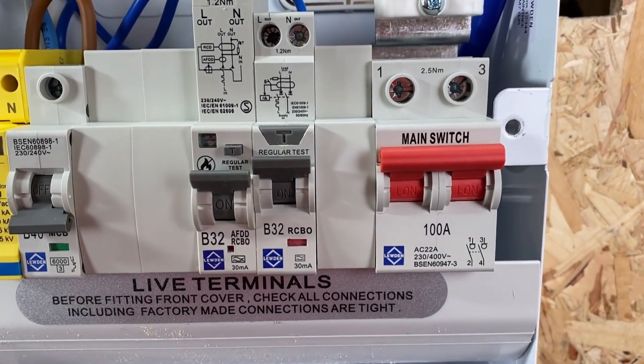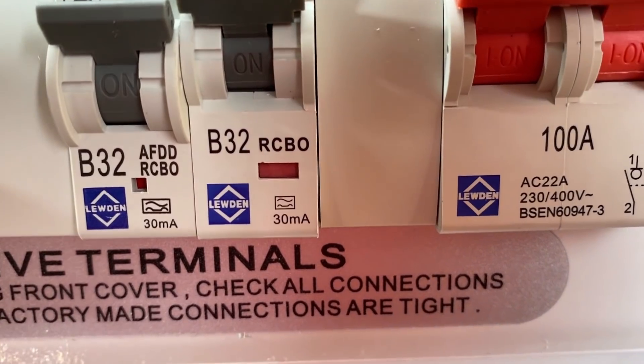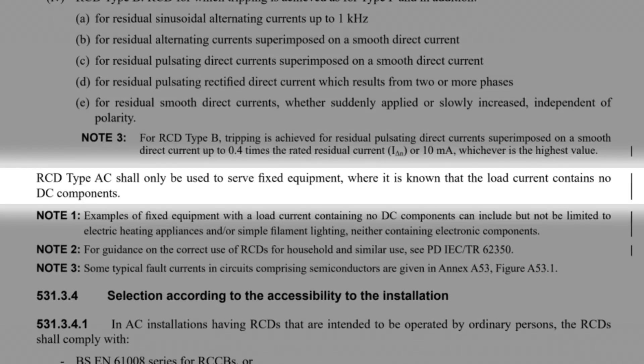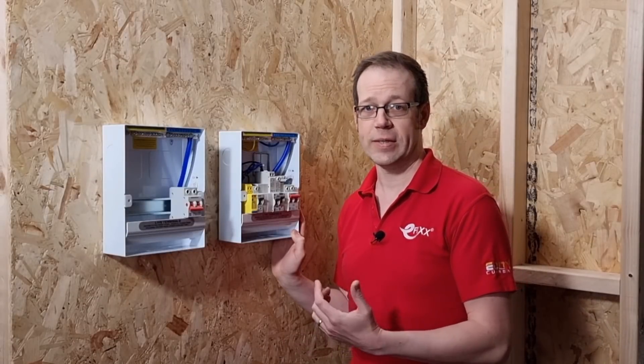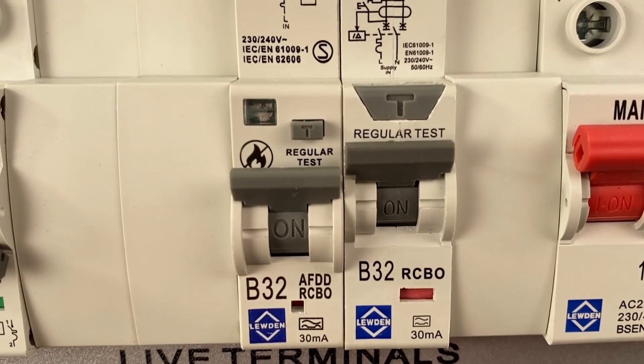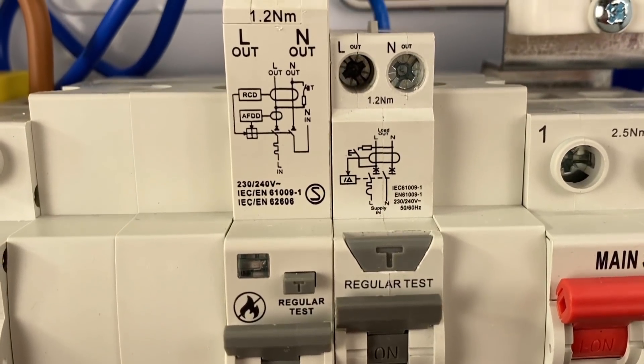Then we've got an RCBO, and looking very closely at that, you'll see it's a Type A RCBO, which makes sense, as under the new amendment, Type AC RCDs can only be used to serve fixed equipment where it's known that the load current contains no DC components — so basically nowhere. And then finally, it's Lewden's new AFDD, all ready for use in compliance with the Second Amendment to the 18th edition of BS7671 in the relevant places.